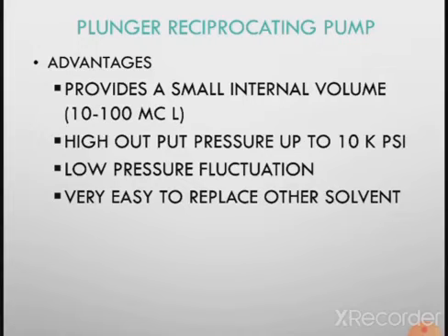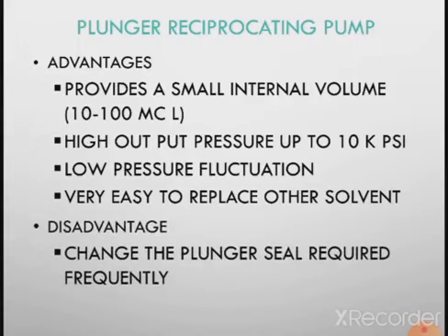Then high output pressure up to 10 kpsi, low pressure fluctuations, and it is very easy to replace other solvents, because it has a very small bore size, that means very small solvent capacity.